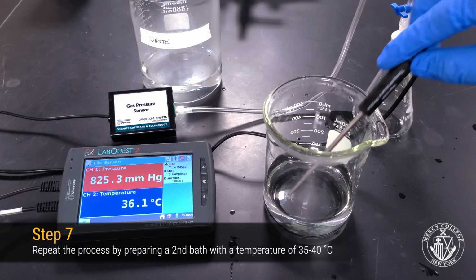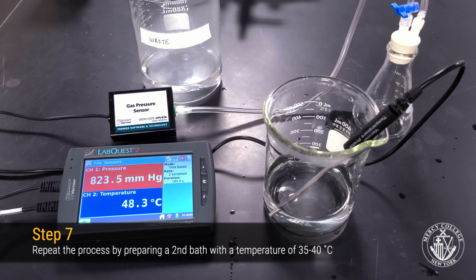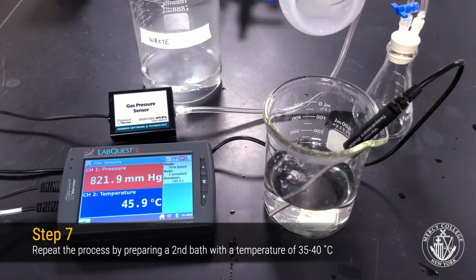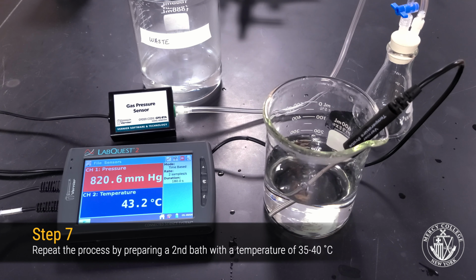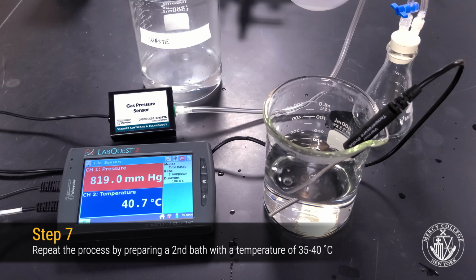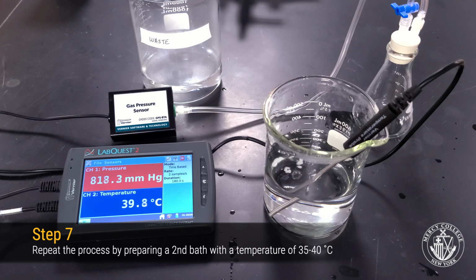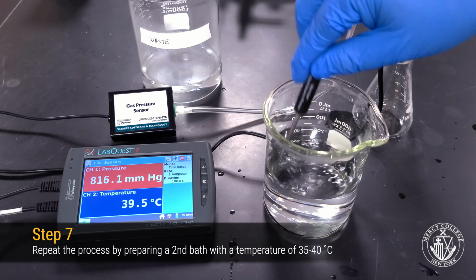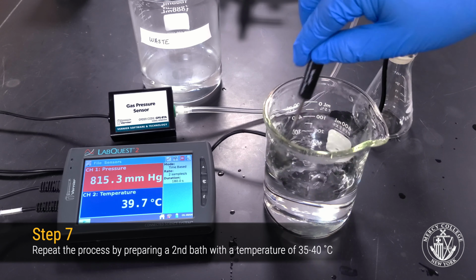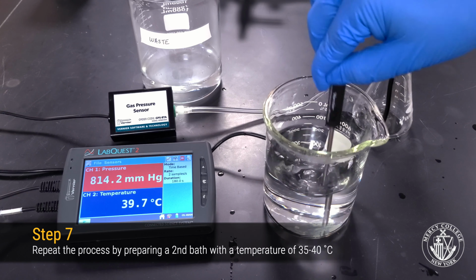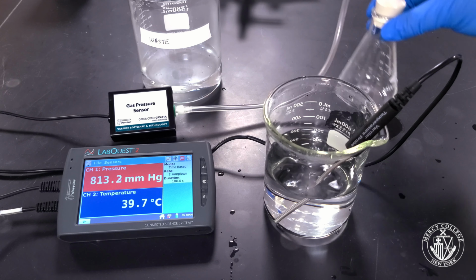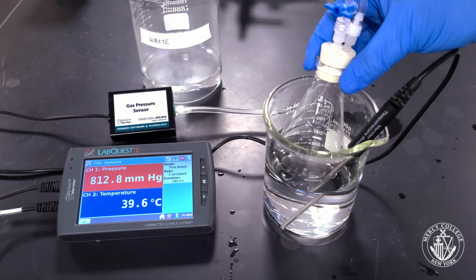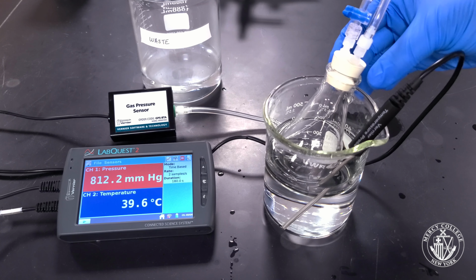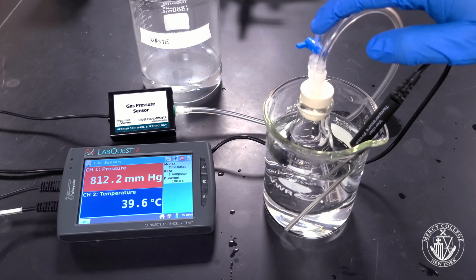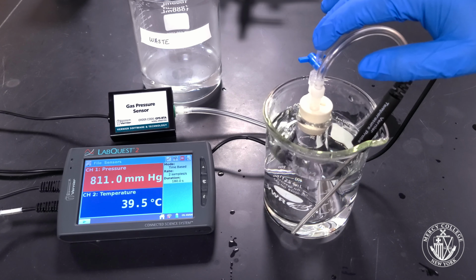We're now going to create a second bath with a target temperature of 35 to 40 degrees Celsius. We're going to do this by adding room temperature water and maybe some ice until we've achieved the temperature that we want. Be sure to stir the bath thoroughly until you've arrived at a constant temperature. If you need to, you can add more room temperature water, more hot water, or more ice. Again, carefully submerge your flask in your bath and move it up and down until the temperature has reached a stable value.